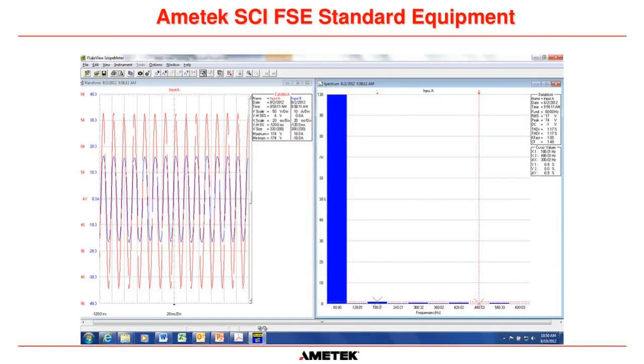And the one last thing that an oscilloscope can do is it can give you mathematically calculated total harmonic distortion readings. Okay, so on the left here you can see we have the voltage and current from a UPS. The red is the voltage, the blue is the current, and what the software within the Fluke 190 allows you to do is you can create this graph here, and it tells you right here what the total harmonic distortion of the voltage out of the UPS is. And in this circumstance, it's 1.17%, which is well within the tolerance of our UPS.